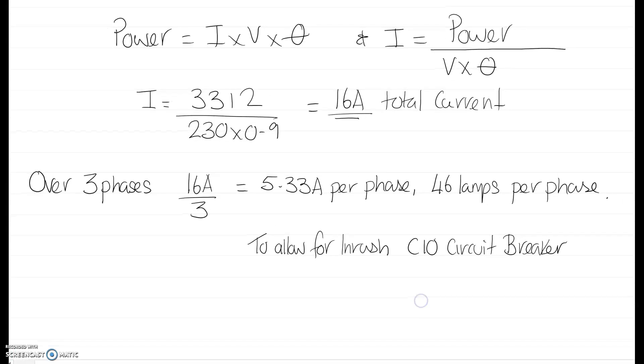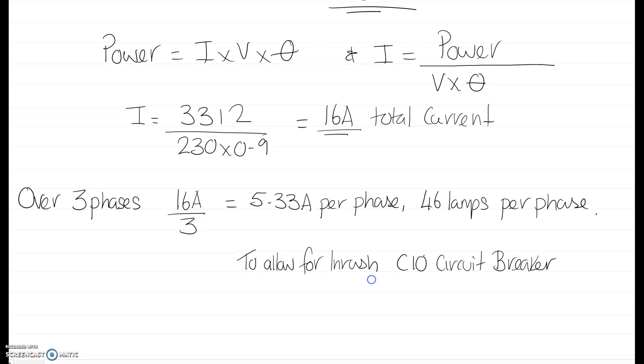Now that's total. Obviously we've got 138 fittings, so we're going to need to divide it up. My advice is to keep it over three phases. 16 over 3 gives us 5.33 amps per phase, and that's 46 lamps per phase, so 46 tubes. To allow for a total inrush, I would probably go for a C10 circuit breaker. Over three phases, and the beauty of doing it over three phases is should you lose a phase in an emergency, you've got another two phases to keep you going.